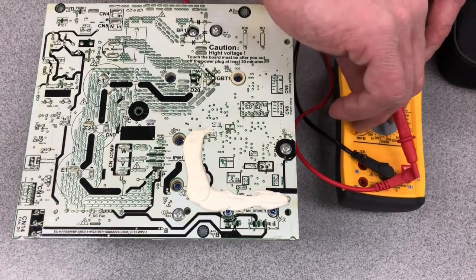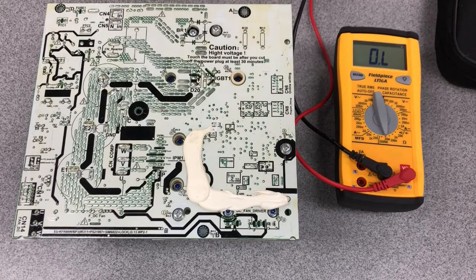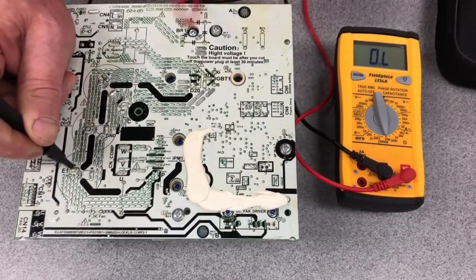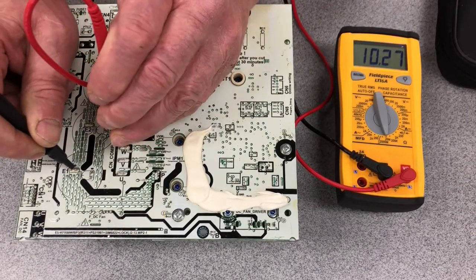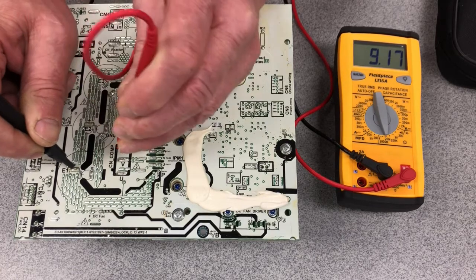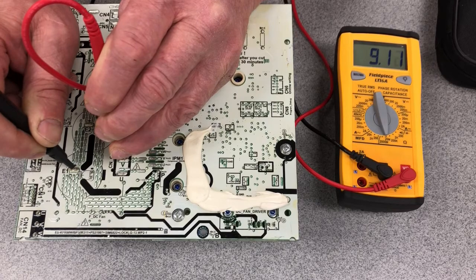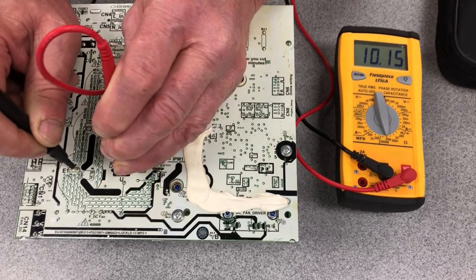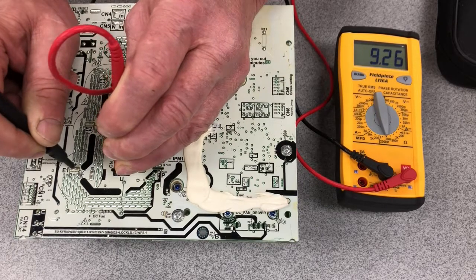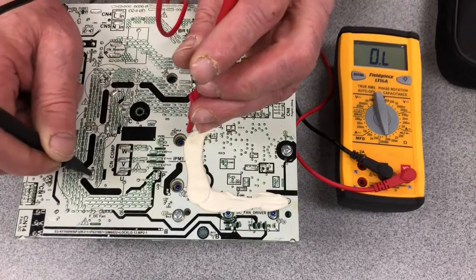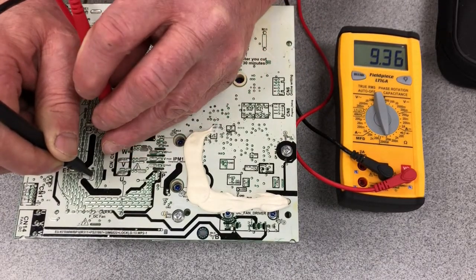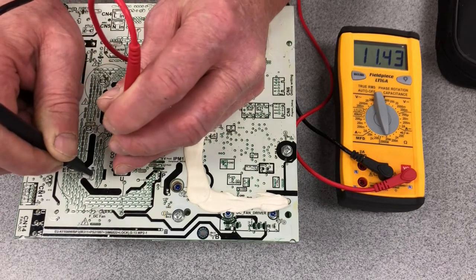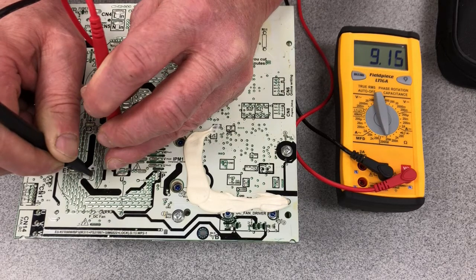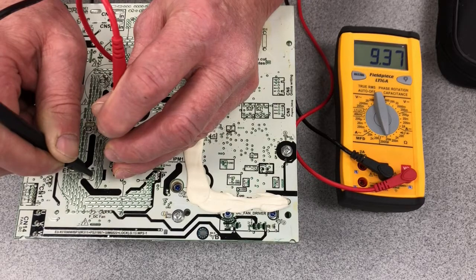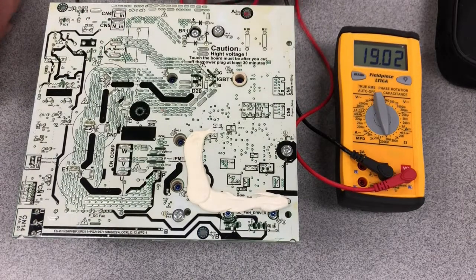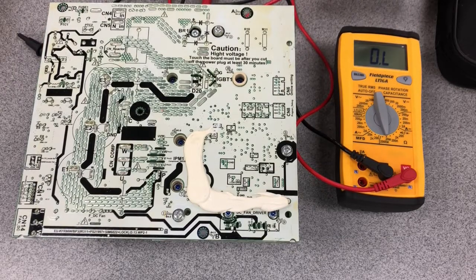I'm going to take my meter and put it on mega ohms. I'll take one lead and go to the positive on my capacitor, take the other lead and go to W - 9.18. V - 9.10. U - 9.26. Now I'm going to take the lead that was on the positive and move it over to the negative, and do it again. W - 9.22. V - 9.16. U - 9.33. So all 6 readings are pretty much consistent, 9.3 to 9.1.